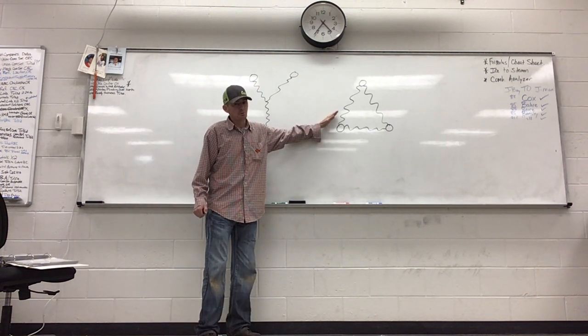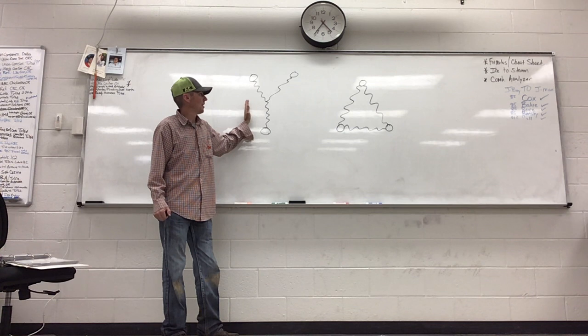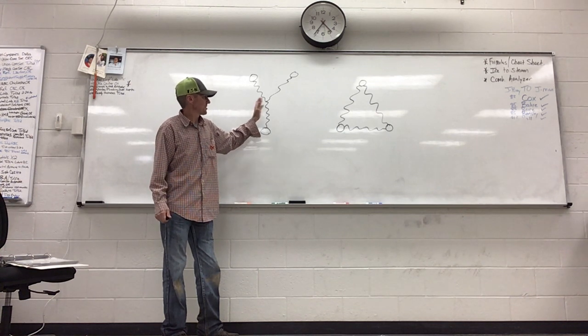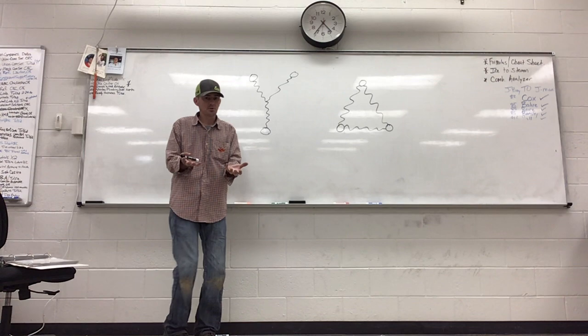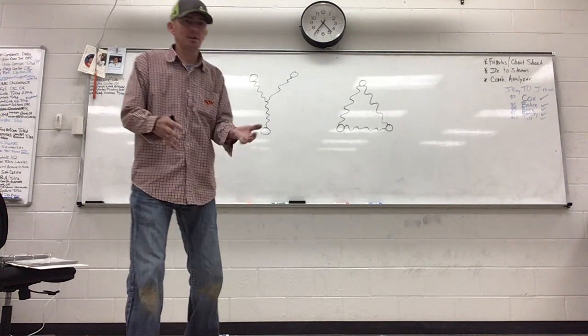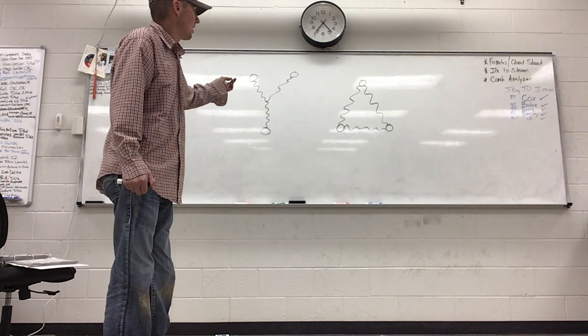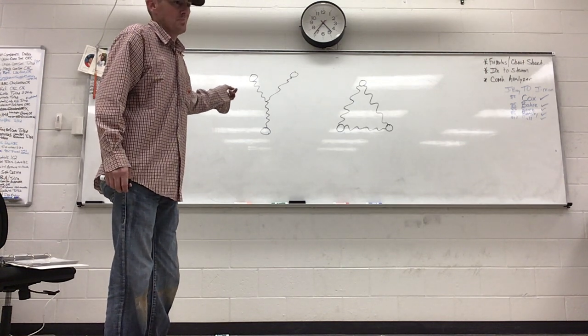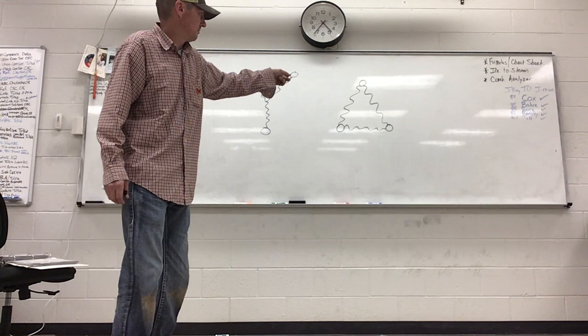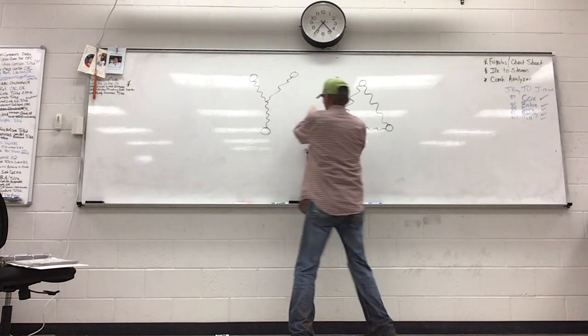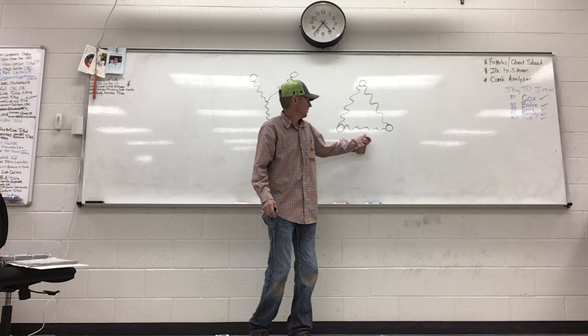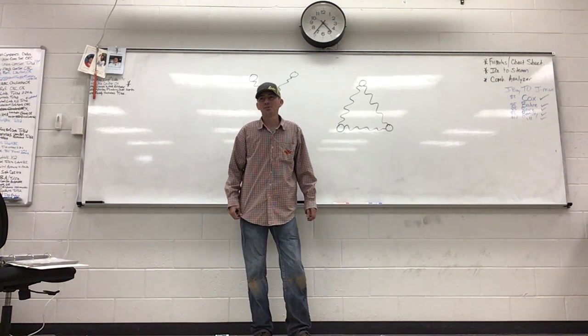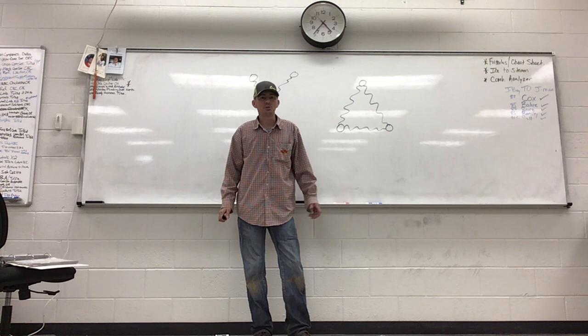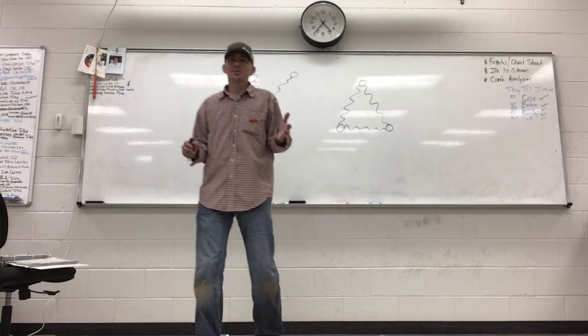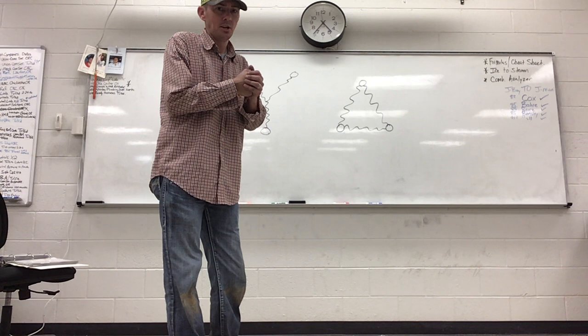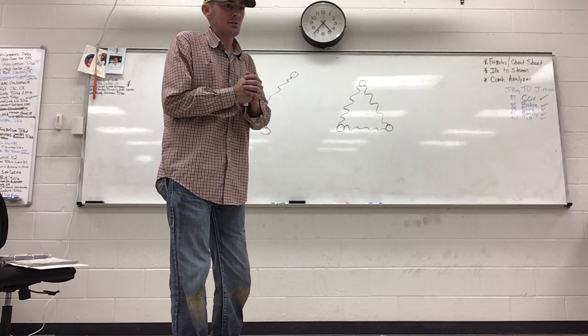Delta is a lot more powerful than Y. From most of the stuff I've read, if you take the same exact motors with the same exact resistance, same exact voltage, everything like that, most of the stuff you read will say that a Y only has about 1/3 of the starting torque of a delta. But what if you're trying to start a centrifugal chiller, or a turbo core or something like that that's spinning 30,000 RPMs? You're not going to be able to take that motor and just close a contactor and start it across the line. We're going to have to soft start it.